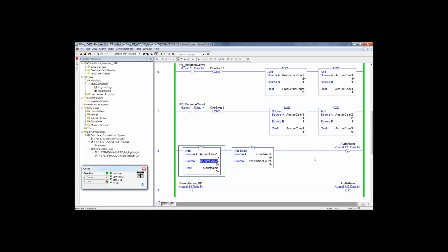There are only 5. We had 6 transitions, true, false, true, or false to true of photo eye 2. But we did not have 6 cartons travel on to conveyor 2. We only had 5. The other one was some other incidental breaking of the optical path that caused the miscount.